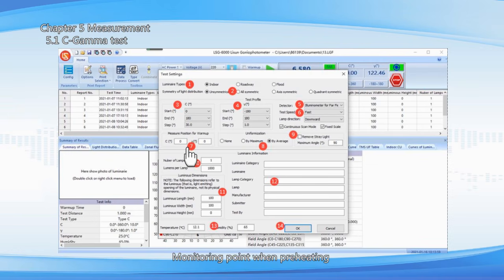Monitoring point when preheating: no need to change. Check by maximum or by average. If not, the IES file can't be opened by some other software. If you want to remove the stray light, check this option and input the angle. The data beyond this angle will be 0. Input the number of light sources and the rated lumen of the light source. If you don't know, just keep it blank. Input the luminous size. Input the information of the sample. Input the temperature and humidity of the darkroom. Click OK to enter the preheating interface or test interface.